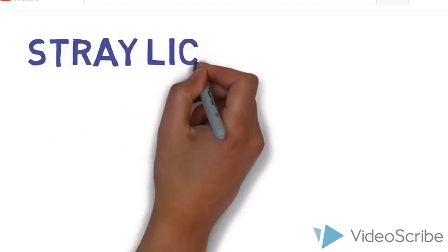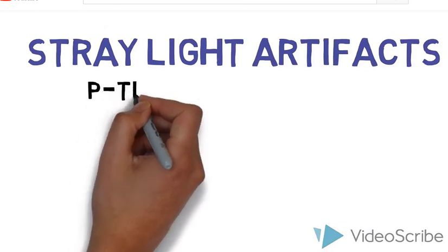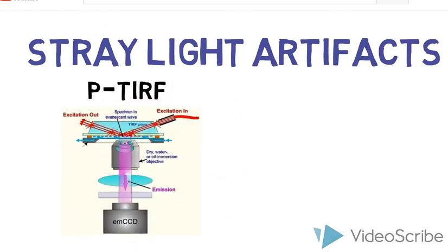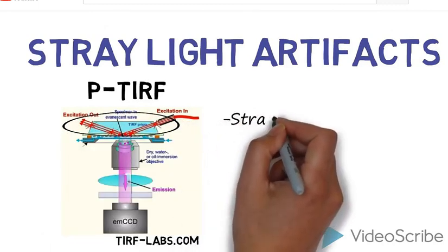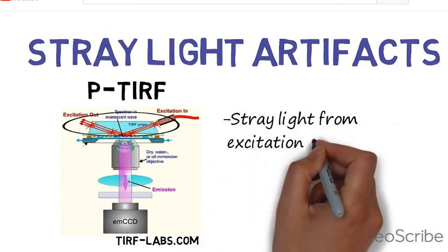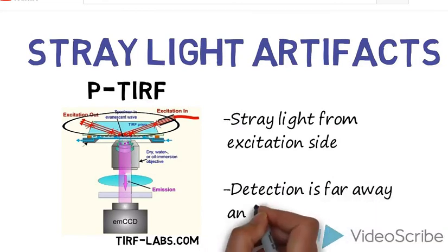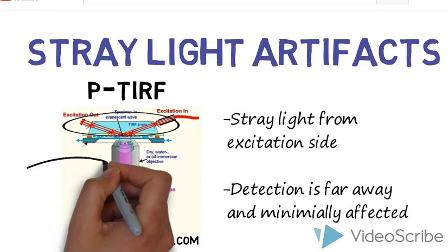To get really nice nanoscale images, one wants to minimize any stray or scattered light that might cause artifacts in detection. In this category, P-TIRF is the preferred geometry. In P-TIRF, stray light can come from scattering at the glass-water interface or at the prism. Because the collection objective is rather far away from these sources, rarely are extra measures necessary to minimize stray light.